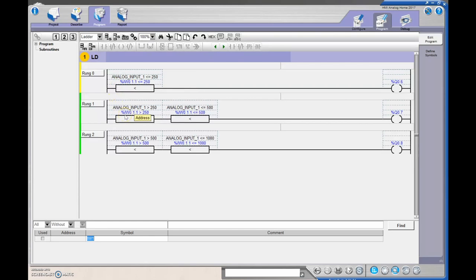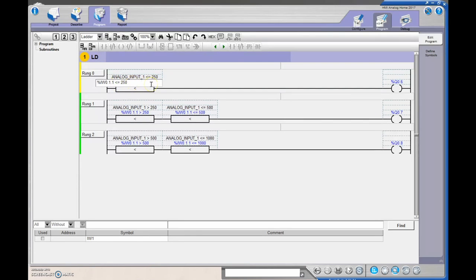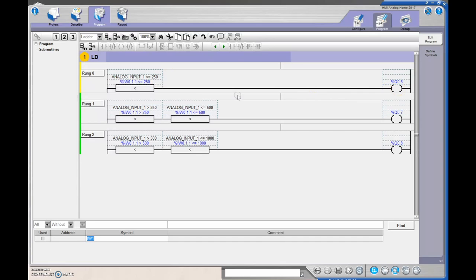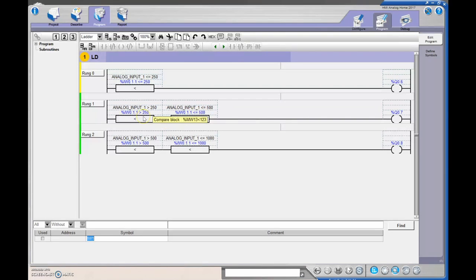So I'm just addressing these guys all the same, %IW1.1. And on the first one, I'm saying that if it is less than or equal to 250, and in my range, that would be 2.5 volts, then fire on my first light. If that word, or that range of 0 to 1000, is greater than 250, but less than or equal to 500, so greater than 2.5 volts, but less than or equal to 5 volts, fire on the second light.